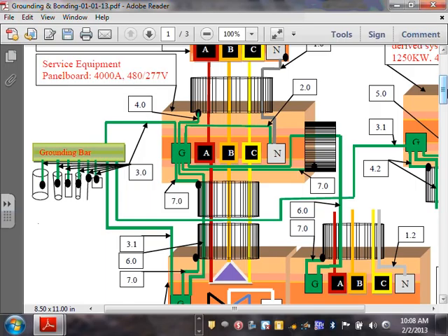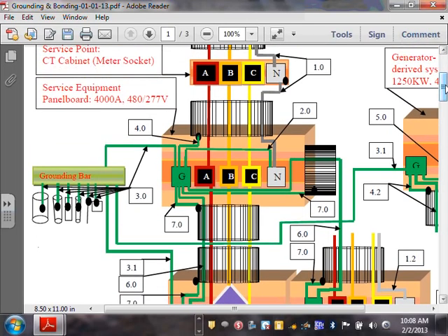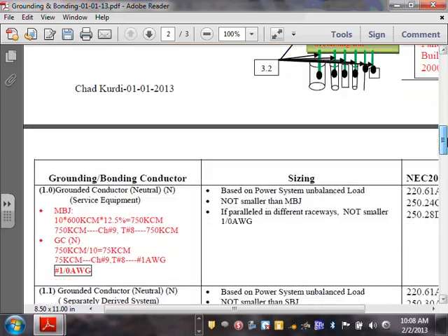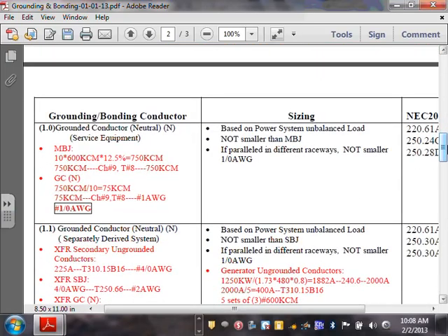We got the grounding. Now I'm going to go flash the calculation that we did. I want to remind you guys, my assumption here is I have a 4,000 amp switch. So I'm sizing for a 4,000 amp switch, and I'm going to go down and size a neutral for a 4,000 amp switch. So just quick here. Okay, number one was the grounded conductor, and you can see that's a grounded conductor, number one, coming to the service. Here's what the code says when you size number one. We need to size a grounded conductor for a 4,000 amp switch. Right? Anybody size a grounded conductor for a 4,000 amp switch here?